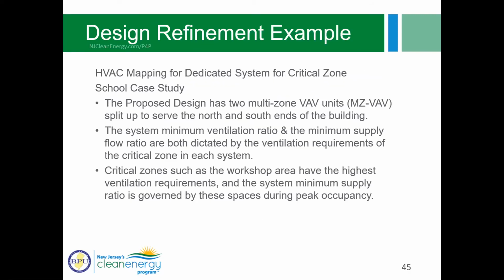So here's an example of HVAC mapping for a dedicated system for a critical zone. And this is a school case study. So what does this mean? Okay, so our initial proposed design has two multi-zone variable air volume units, called MZ-VAV, and they're split up. So there's two of them, one serves the north and one serves the south end of the building.